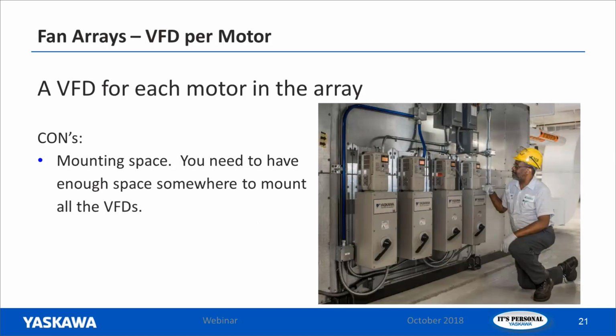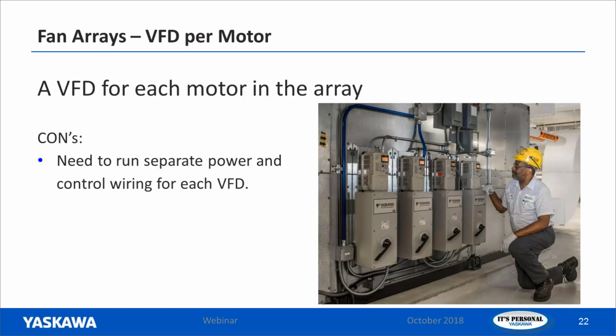Another thing to consider would be mounting space. So again, if you're using a VFD for each motor in the array, you do have to have a place to mount these VFD packages. Over here on the right, you see we've got 4 E7 packages running a 4-motor array. And in this particular case, they did have the mounting space, so they had enough real estate there to mount them, and it looks pretty good. But you do need to run separate power and control wiring for each VFD, so that could start getting you into a little bit of trouble.